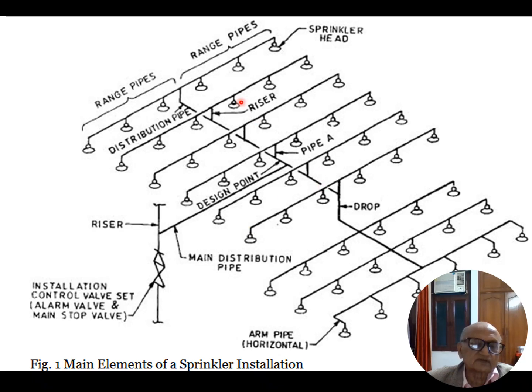the several sprinkler heads are provided in a particular range, and range may be on both the side of the main distribution pipe. Main distribution pipe is this. This is drop portion of that rising system, and this portion is known as arm pipe, horizontal. These are all horizontal. This is horizontal. The only vertical portion is this, or this, or this. There are three verticals, this or this.